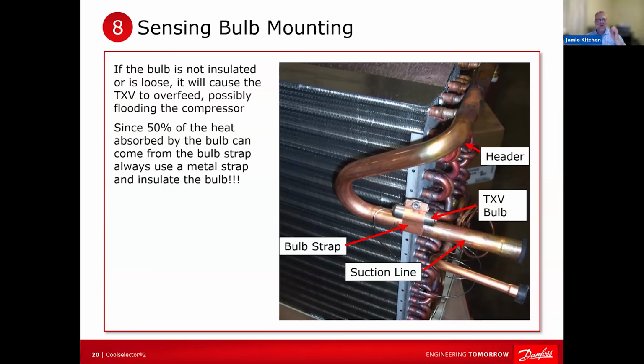So I really don't care whose bulb strap you use, as long as it's metallic. All right. If it conducts electricity, it conducts heat. I'm not telling you to test that out, right? But remember that, okay? It does. So make sure it is strapped to the pipe. Don't crush the pipe, but it should take a lot of effort to move that sensing bulb because you don't want anything underneath it, right? That could cause that.